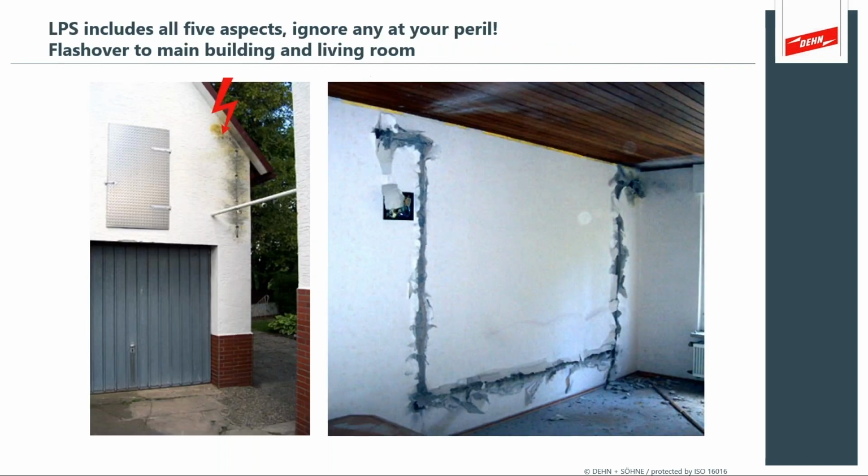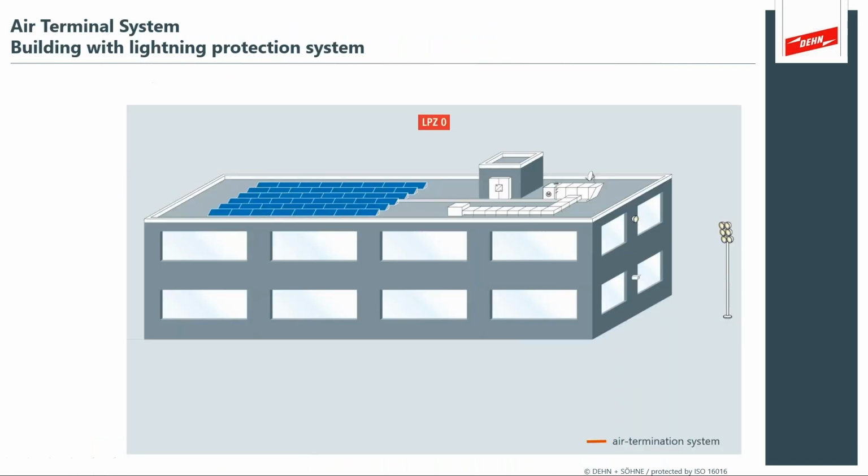So what's happening? You're getting lightning into a building and it's flashing into the electrical wiring. If you don't pay attention to all 5 aspects, you can have any combination of damage. What's interesting about this photograph is that there was a down conductor system maybe along the outside, but it flashed into the internal electrical wiring. And this, of course, would have caused lots of fire damage.